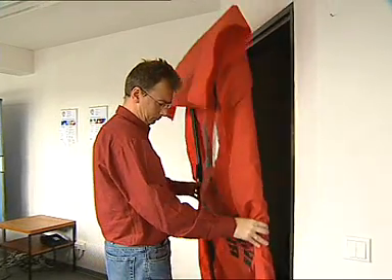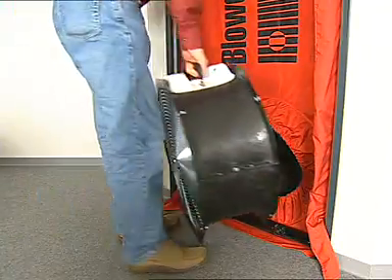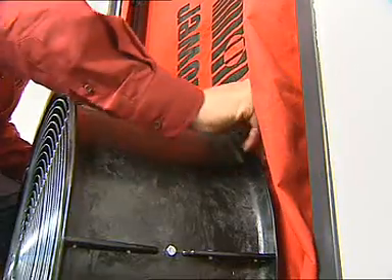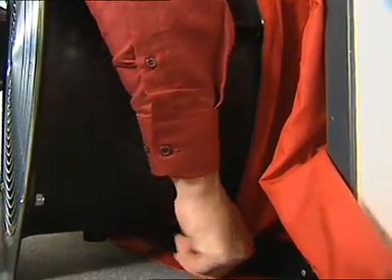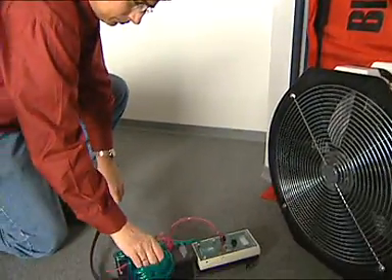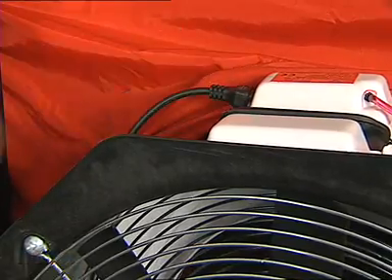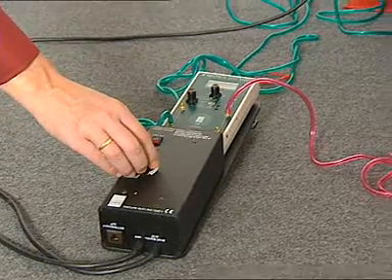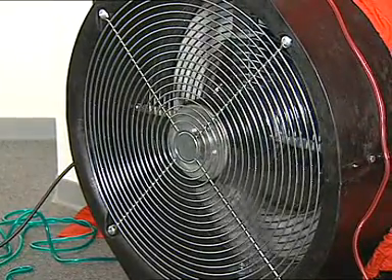Another use is the detection of air leaks by identifying the air change rate with the help of what is known as the blower door process. This process creates underpressure in the building. Since the air pressure outside the building is higher than the pressure inside, air will try to enter through unsealed areas.